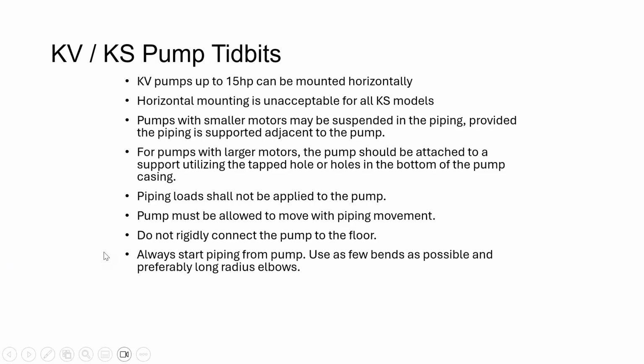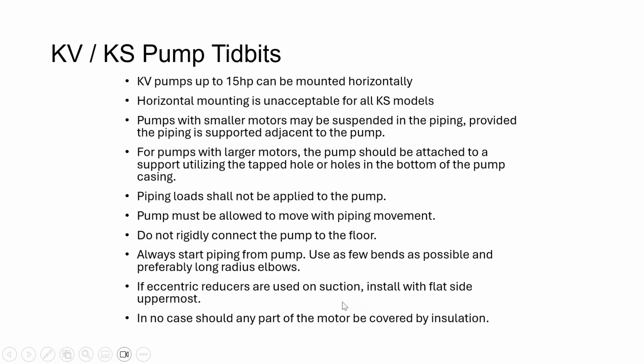And this is just common for all pumps. Always start piping, when you start laying out and installing the piping, from the pump, and use as few bends as possible, preferably long radius elbows, would be my statement in that regard. And if you're using an eccentric reducer on suction, install it with the flat side up. That helps the flow going in. And in no case, and this is very, very important, do not insulate the motor. So the motor can't be covered with any insulation. So these are very, very important.